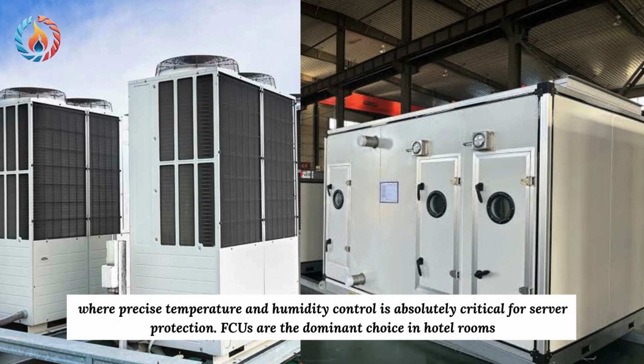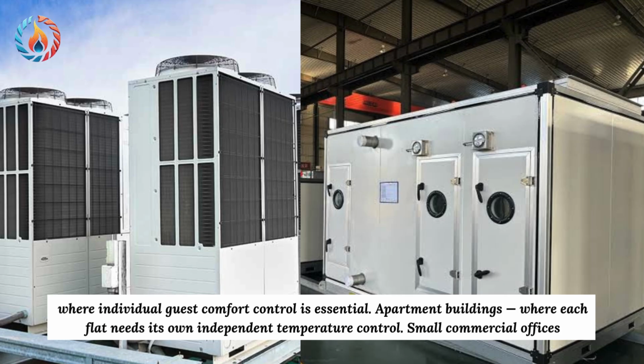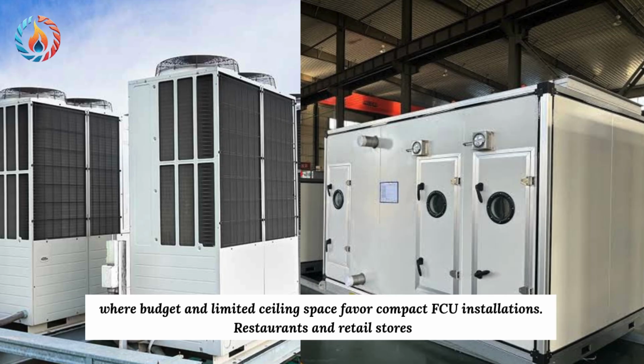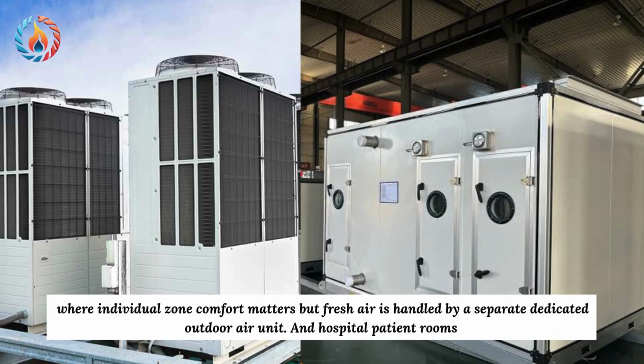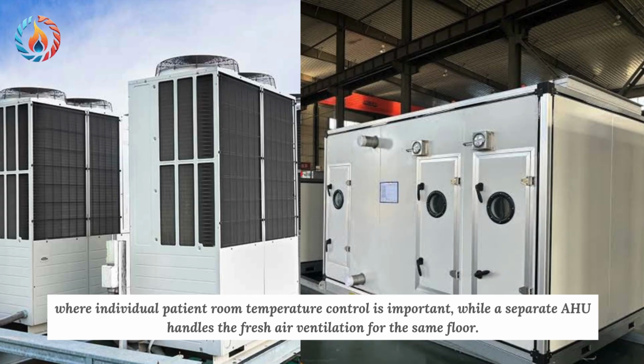FCUs are the dominant choice in hotel rooms, where individual guest comfort control is essential. Apartment buildings, where each flat needs its own independent temperature control. Small commercial offices, where budget and limited ceiling space favor compact FCU installations. Restaurants and retail stores, where individual zone comfort matters, but fresh air is handled by a separate dedicated outdoor air unit. And hospital patient rooms, where individual patient room temperature control is important, while a separate AHU handles the fresh air ventilation for the same floor.